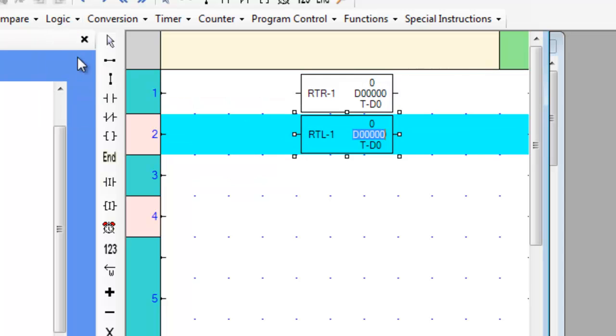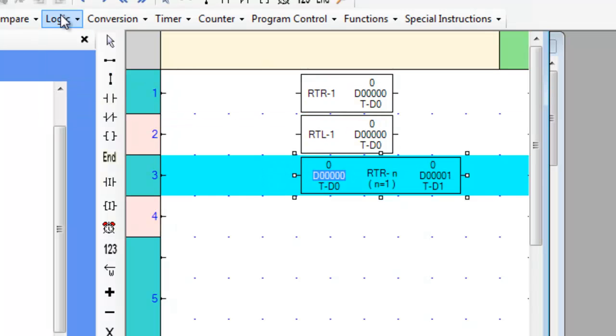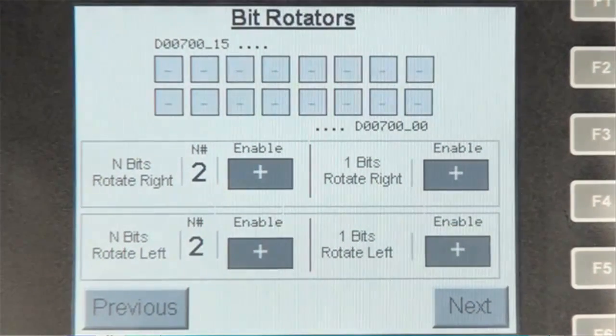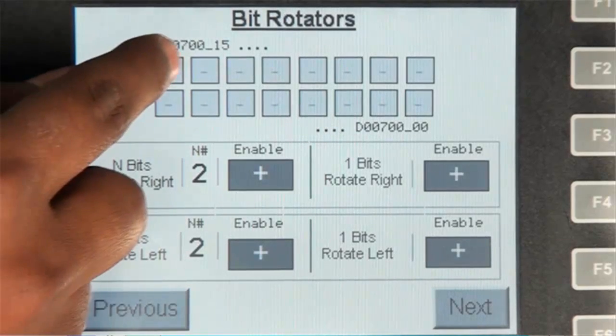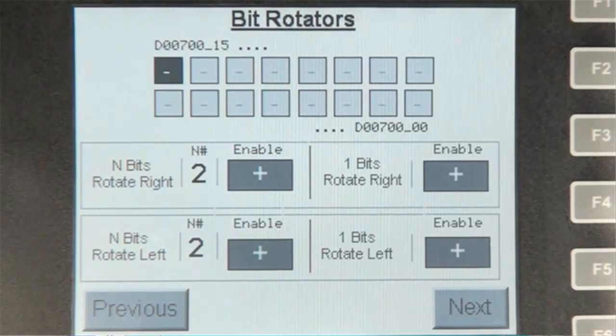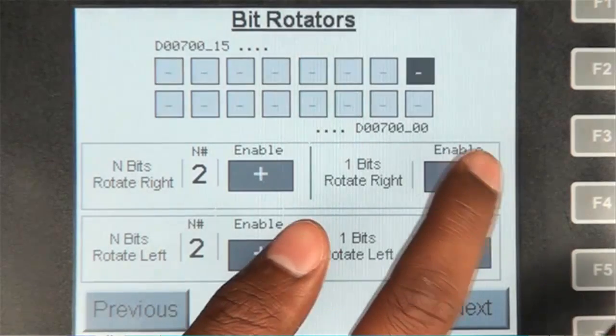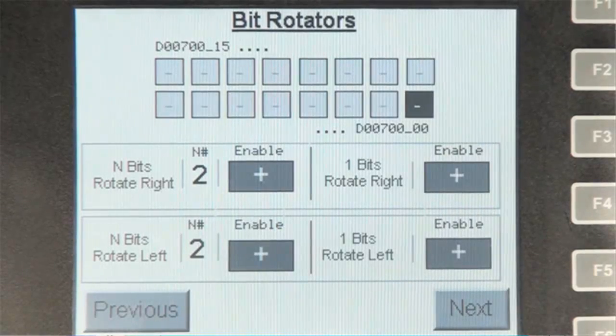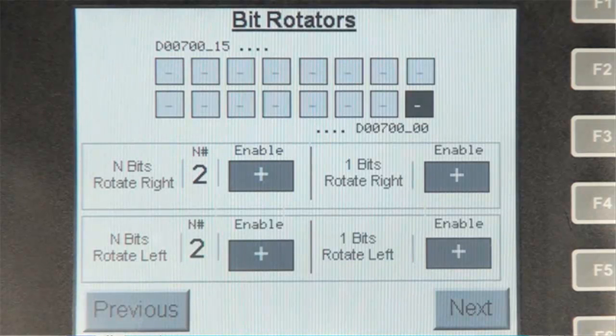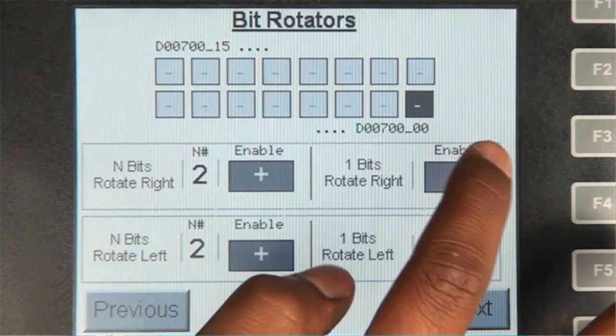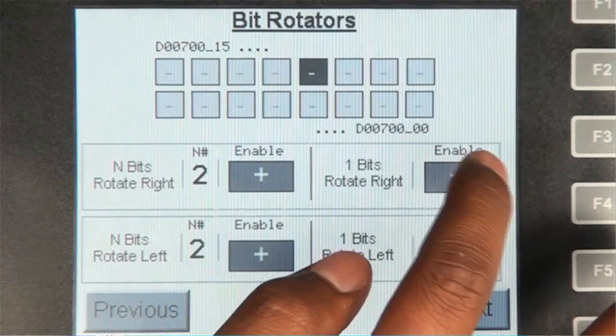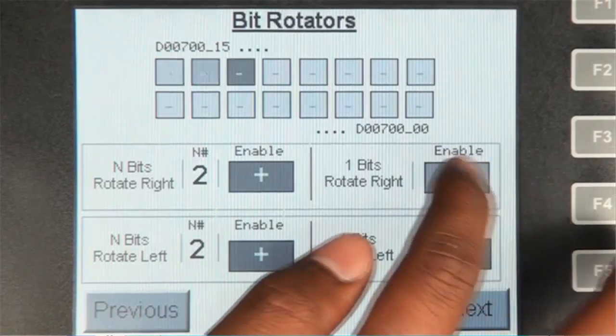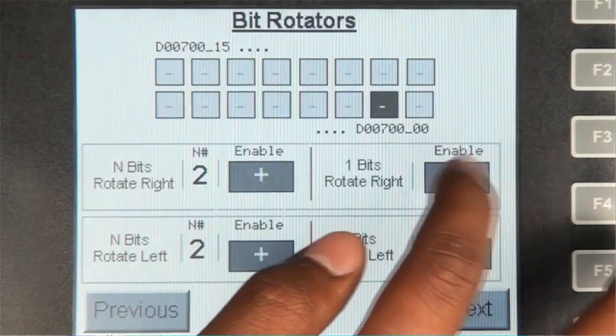Now that we know where they are and what they look like, let's go over to the HMI and examine the instructions. On the HMI, let's turn on D700's 15th bit, then press the 1 bit rotate right enable button and keep pressing it until it reaches the 0th bit. Now let's press the enable button one more time — the bit is rotated from the 0th bit back to the 15th bit. This rotation is the major difference between the shift and the rotate instructions.